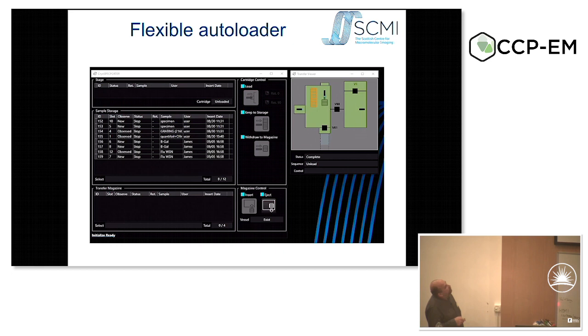the stage. So what this means is we can load 4 grids at a time, move them into storage, image them, take 2 out, put another 4 in, take 3 out. You can leave a grid in there for 2-3 weeks if you want to, or months if you need to. That also means this storage area is not vented regularly. It's only vented when we warm up the autoloader. So this all stays under vacuum, which keeps it very clean, which is very nice.